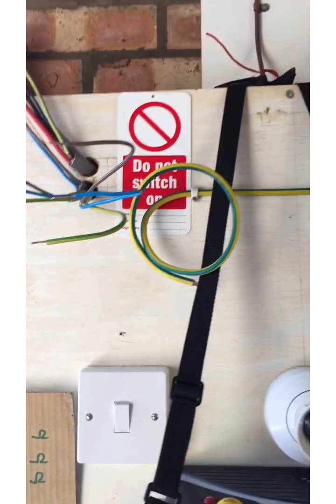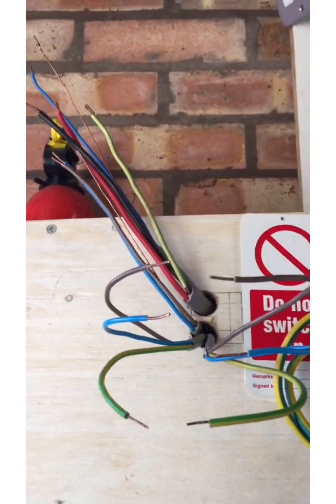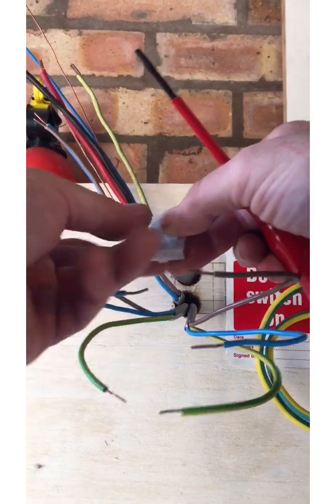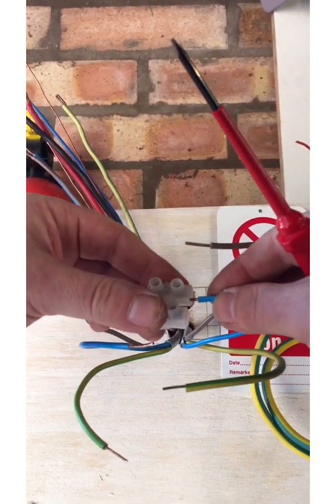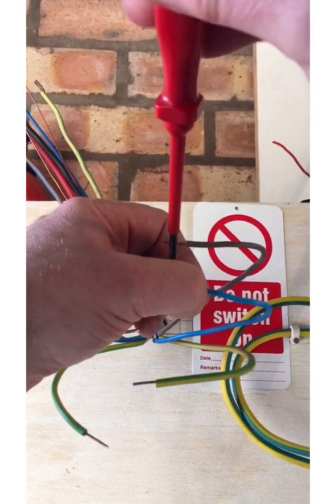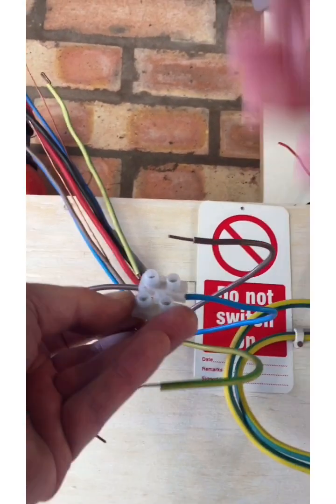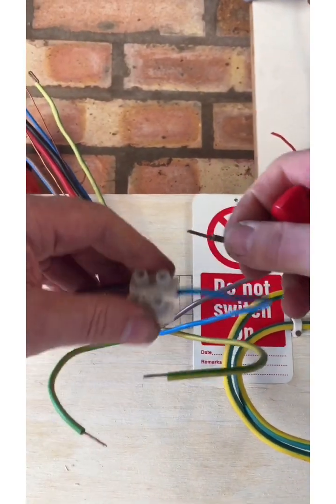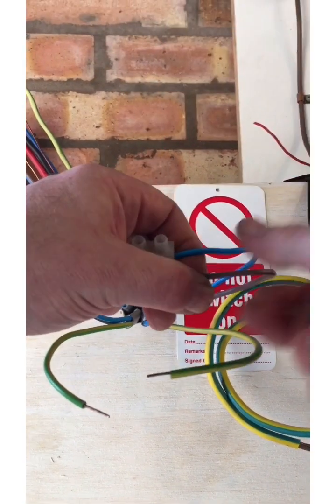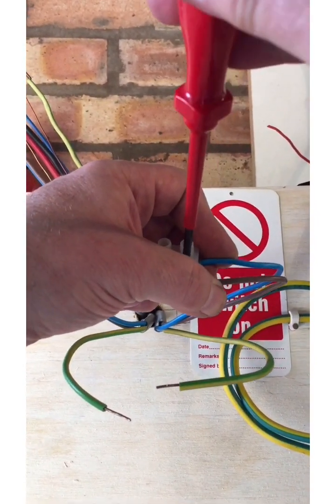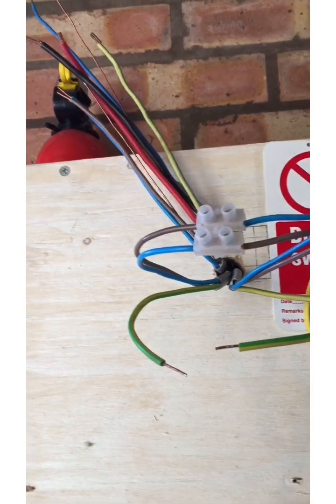If we go to step two, now step two involves reconfiguring the way that these are set up here. And this is called the figure of eight connection between the line and the neutral. Now what we're doing here is we're taking the incoming line, so you can see that, and connecting it with the outgoing neutral. And here we've got the incoming neutral, and we're connecting that with the outgoing line. So there we go. That's our figure of eight connection.